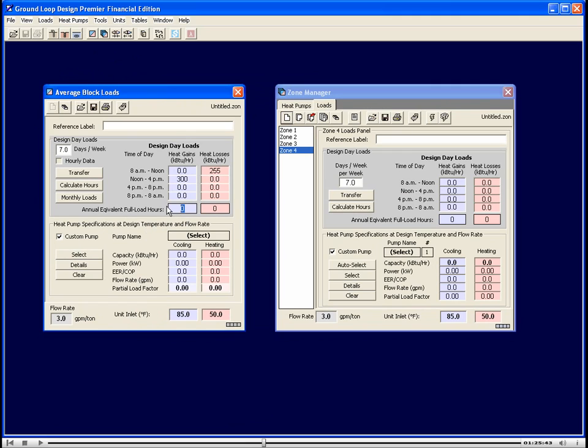On the cooling side, perhaps we have 1500 hours. On the heating side, maybe 1200 hours. If we take this 300 KBTU per hour peak and multiply it by 1500, that will give us the total KBTU or MBTU for the entire year.